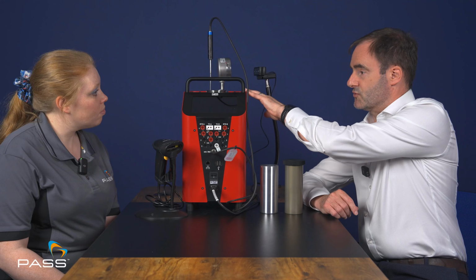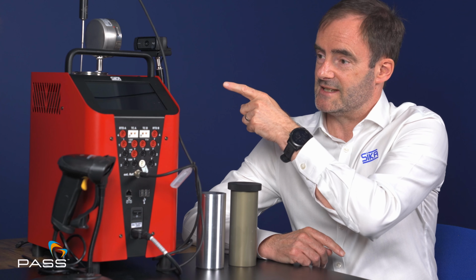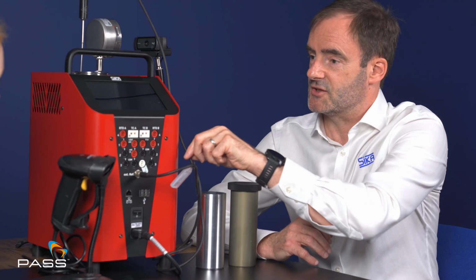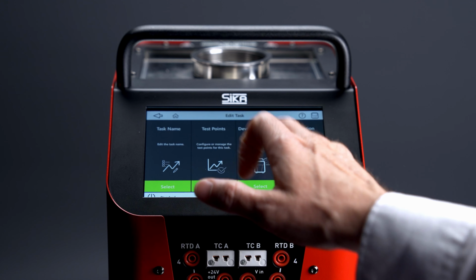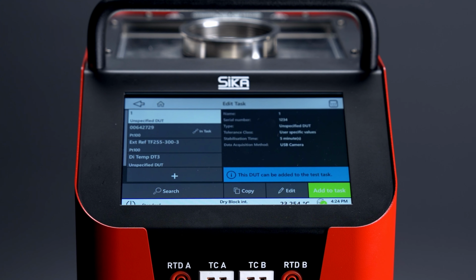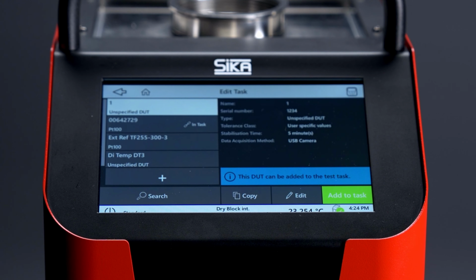But basically what we have to do, first of all, is decide which of the inserts are inside the unit. In this one, it's a dry block, so we pick the dry block. And then we pick the linearization software that's inside the unit. We choose that device. And then we talk about the device under test, which is the customer's product. And then we also choose whether it's an external or an internal reference sensor that we're using. Once we have those set up, we can then pick how many different temperature points, because of various temperature ranges we can use. So some customers would use 3 temperature points, 4, 5, however many they need.